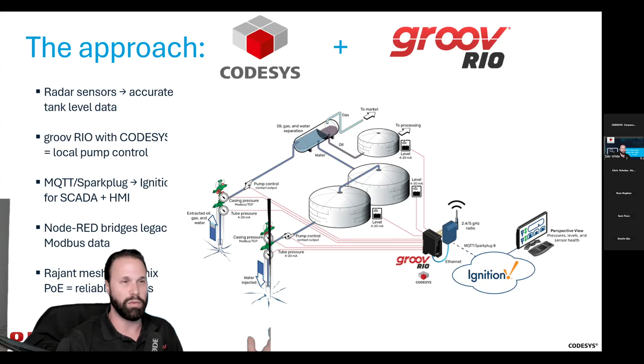The big result was they prevented the spills we talked about. Since implementing this solution, they haven't had a single spill. Each one would have cost about $200,000 just operationally, not including environmental or regulatory fallout. They've now got quality, reliable data along with real-time pump control, all tied to real-time tank levels, so operators aren't stuck running out doing manual checks. Instead, Ignition gives them full visibility across their sites with alarms and the historian built in.